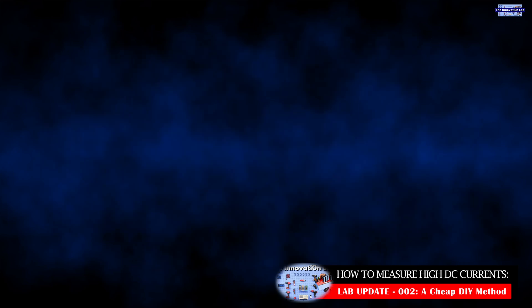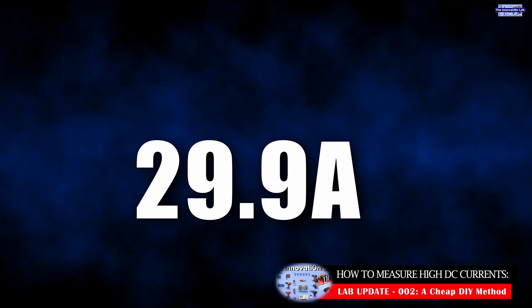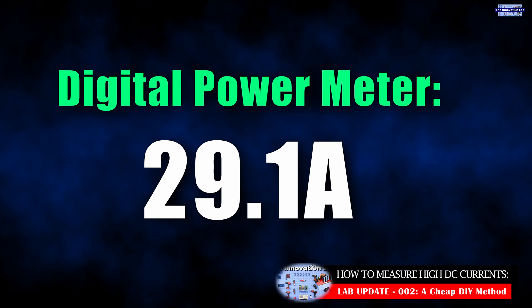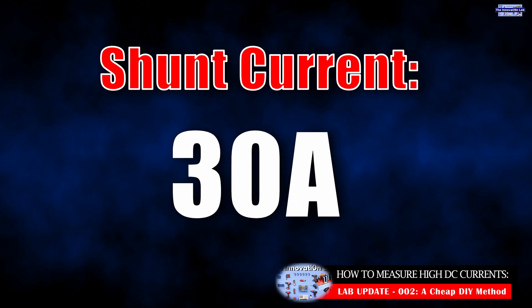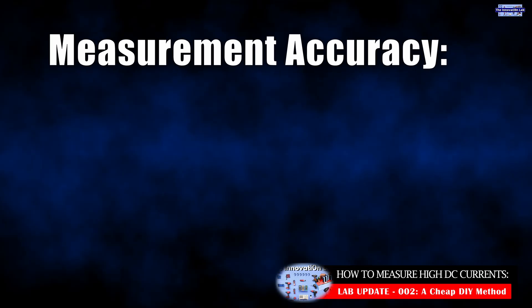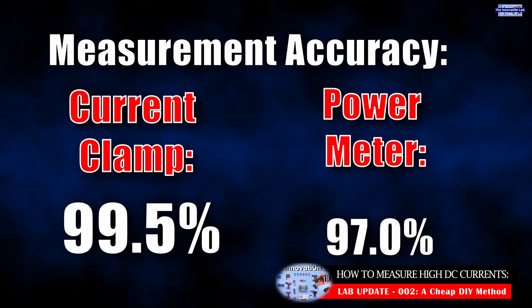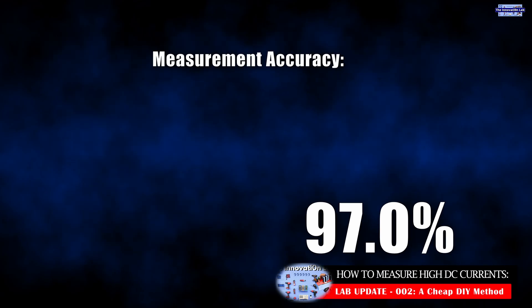During the test, the digital current clamp measured 29.86 amps and the digital power monitor measured 29.1 amps. When we compare these with our calculated value through the shunt — which is 30 amps — we're seeing a measurement accuracy of 99.53% on the current clamp and a measurement accuracy of 97% on the digital power monitor.